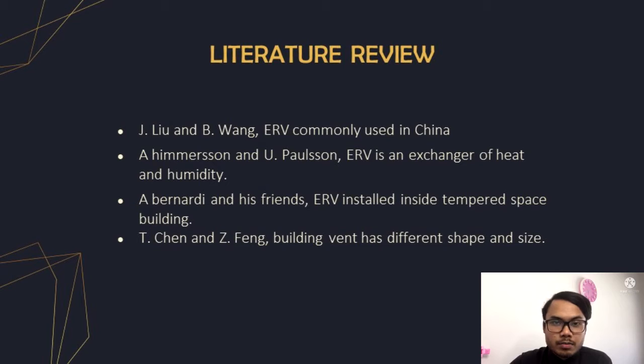The third research paper is from A. Bernardi and his colleagues. They state that the ERV is installed inside the tempered space of the building, normally in the mechanical basement area near the outer ports. Other possible locations include a wardrobe, a laundry room, a workshop, or even the garage. Commonly, designers hang it from the ceilings.